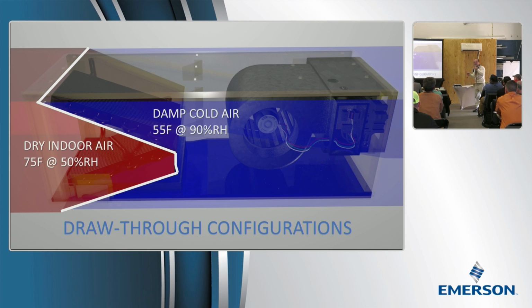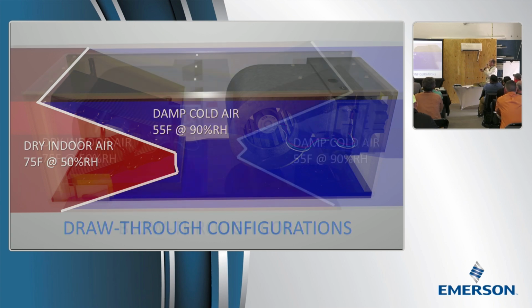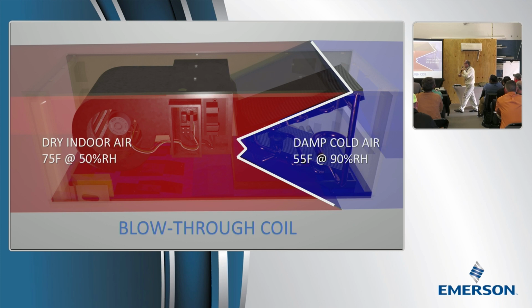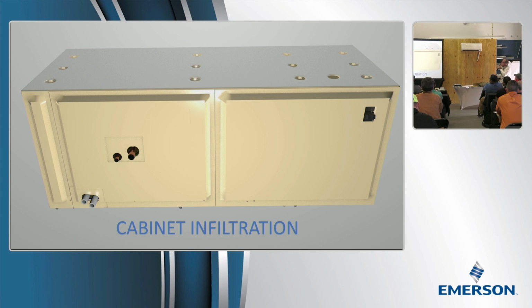One that sweats really differently, no brand names, nobody yell it out. Don't yell it out. Don't do it. This is what we call a blow-through, right? The air handler's blowing through the coil. The only part of it that could sweat is here. That's it. The rest of it's at the low dew point, but it's not cold enough. It can't sweat. So it's not going to be the same with every single air handler. This is the big one that everybody could do something about tomorrow morning if they just gave a damn. That's the main ingredient.